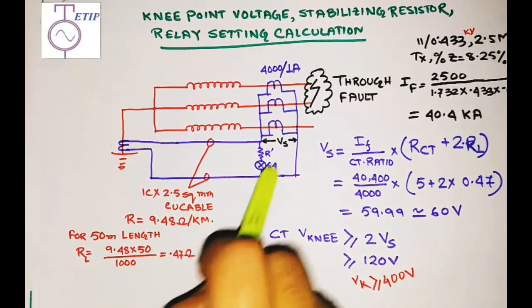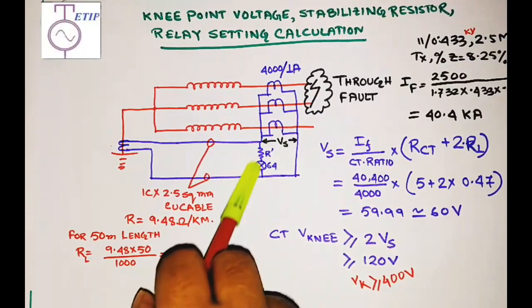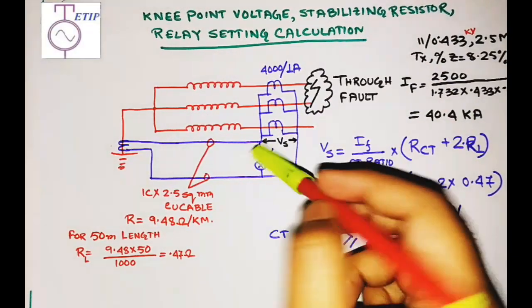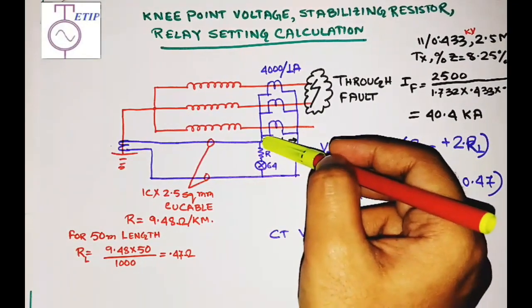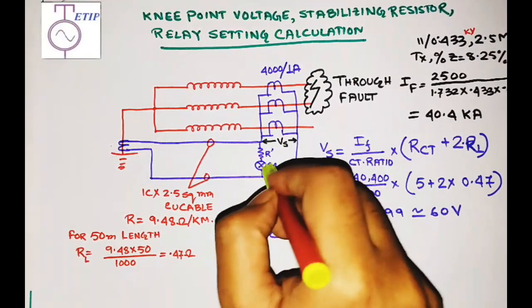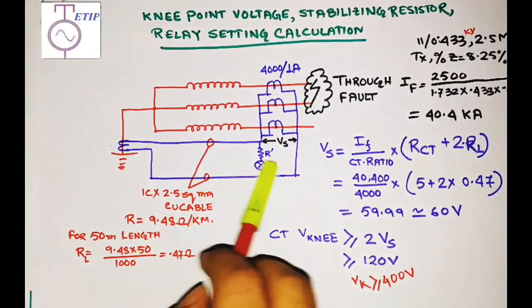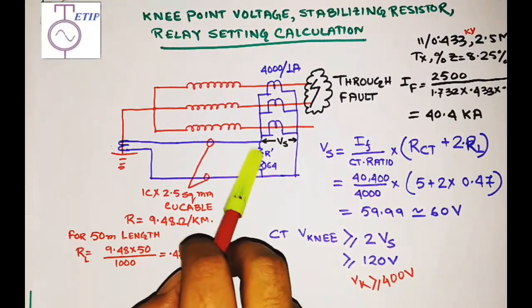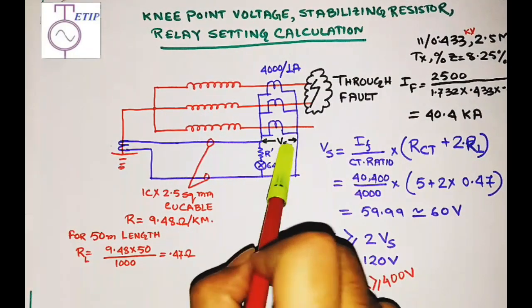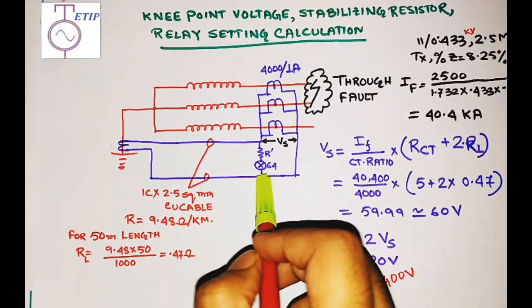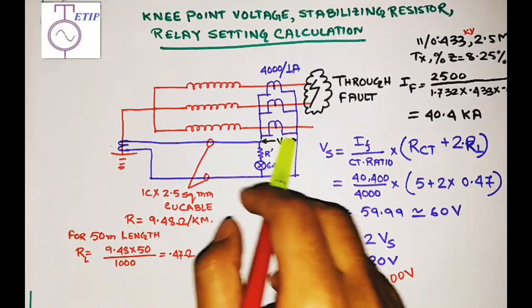Earlier I said that this stabilizing voltage Vs will try to drive a current through the relay coil. I have to make sure that the current flowing through the relay coil due to this voltage is less than the pickup current of the relay. To achieve this, we place another resistance called the stabilizing resistance. This resistance limits the current so the relay does not pick up. Let us see the calculation of this stabilizing resistor.